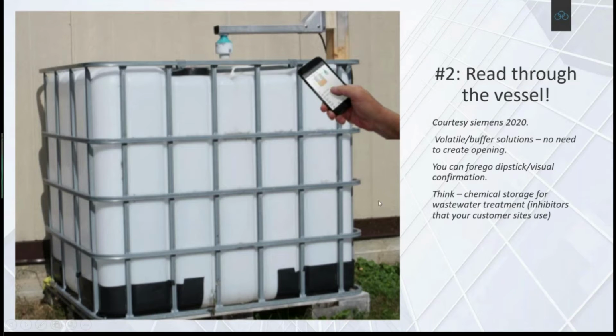This is a case that's attracted a lot of attention, not just from people familiar with PI, when you've got certain volatile materials or certain dyes and chemicals you wouldn't want to open up, kind of harsh or aggressive - then you can read through the IBC itself. It will read through the plastic polymer. You set it up on a mounting flange, and that will read through to whatever level. So you don't have to go around with the dipstick, don't have to compromise, don't have to bring the safety team on board just to waste their time. You're passing by with your app, you select through your relevant LRs that are paired up, and you can check the level at a glance.